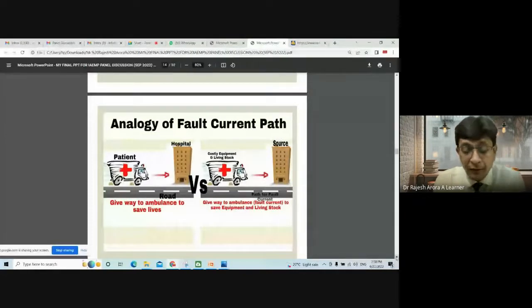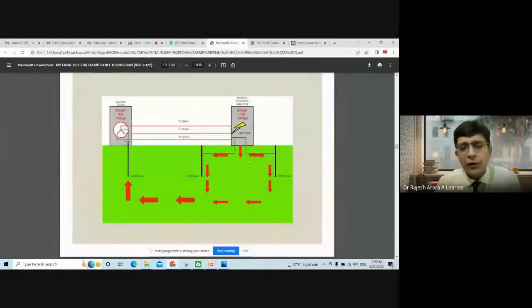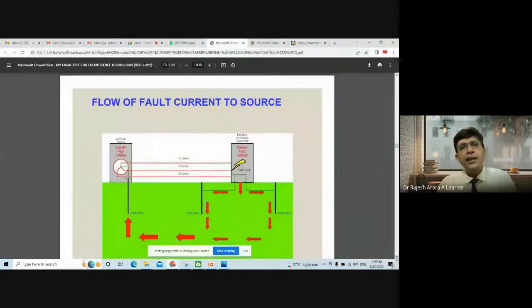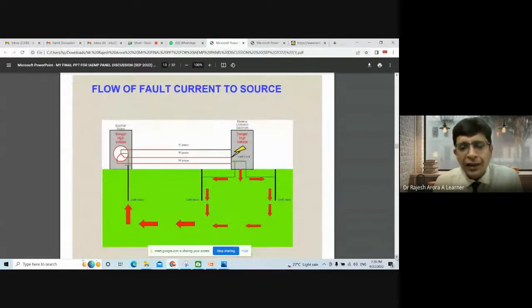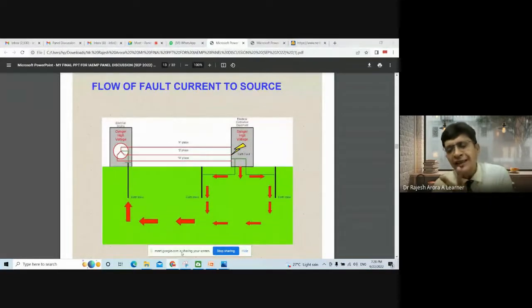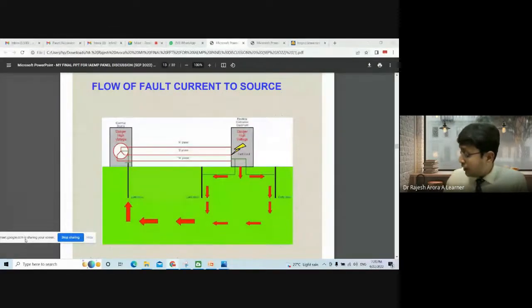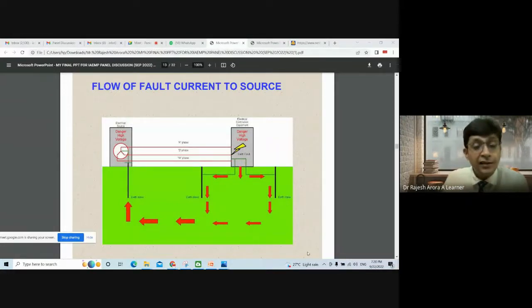What happens when we talk about short circuit? Whenever the term short circuit is used, the meaning is very simple: your phase wire is touching earth or neutral. That becomes a short circuit. When it is touching the neutral, that's not a big issue. In that case, the relays can operate and these MCBs will come into the picture. But when it is touching the earth, the only device that can save you is your RCCB, residual current circuit breaker. RCCB or ELCB is the older name. This device can be used, and you have to be very careful.